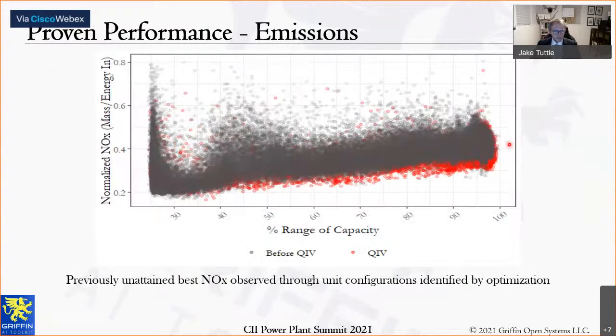And another key thing that was possible here was that the system was able to realize NOx emission rates that had never been realized before by operators or anybody else running the unit. The optimization system in Griffin systems is capable of finding new configurations to outperform anything that's been seen previously in the historical data.